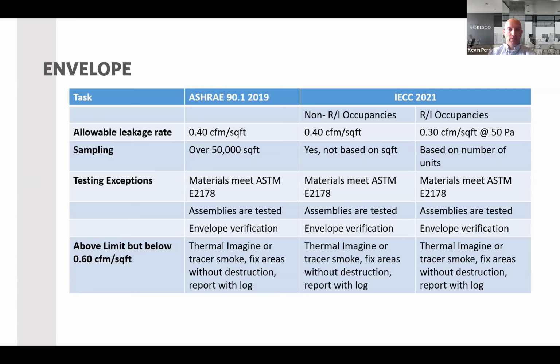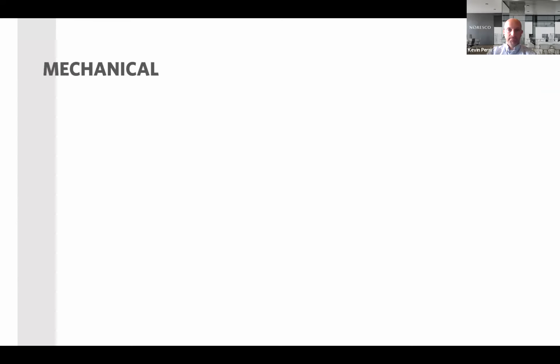Then you also have to send a separate report with the log of items found during the thermal imaging or tracer smoke, and then any items that were corrected, and what measures were taken to correct them. So that is probably by far the biggest category that I see for similarities and differences in envelope, this envelope testing or leakage category. So with that, that wraps up the envelope section.